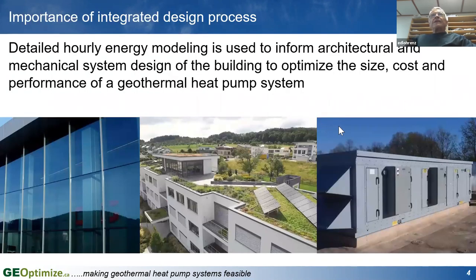So one of the things that we've really concentrated on, to make these systems more cost effective to build and to operate more efficiently, is to look in a fair bit of detail at how the building is being constructed: what kind of glass is going into the building, what kind of roof is going onto the building, how the fresh air is supplied to the building. All of those things can have a huge impact on how much energy you've got to push into the ground or pull from the ground. So looking at those things in detail will change the amount of energy that you've got to deal with, and will change the size and the cost of the ground heat exchanger.